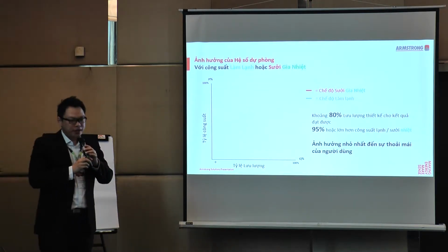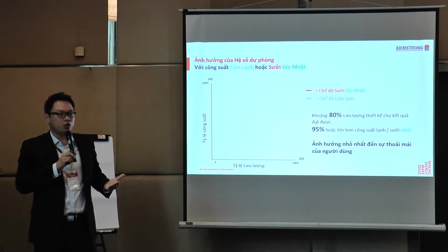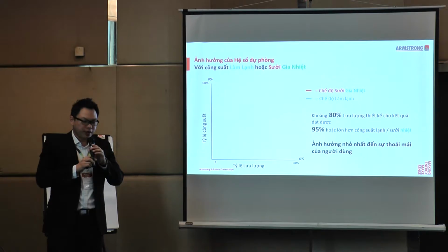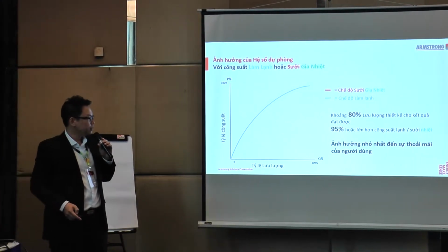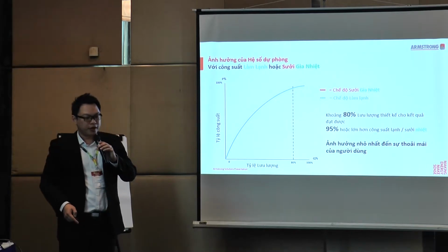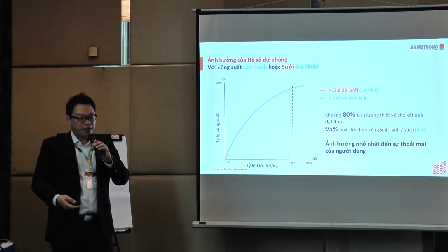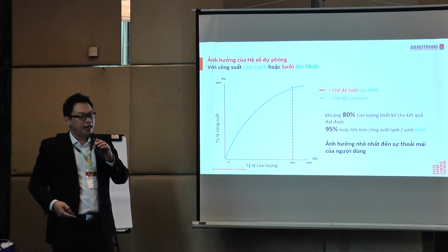So what effect does 80% of the design flow have on the cooling coil as well as the heating coil? Based on this graph, at 80% flow, you're still able to have 95% of the cooling coil emission. And at 85% flow, you're able to have 98% of the heating coil emission. So what does this mean? That means even though you do not have 100% redundancy, there is still a minimum comfort level for your occupants, even if you're operating at 80% design flow.